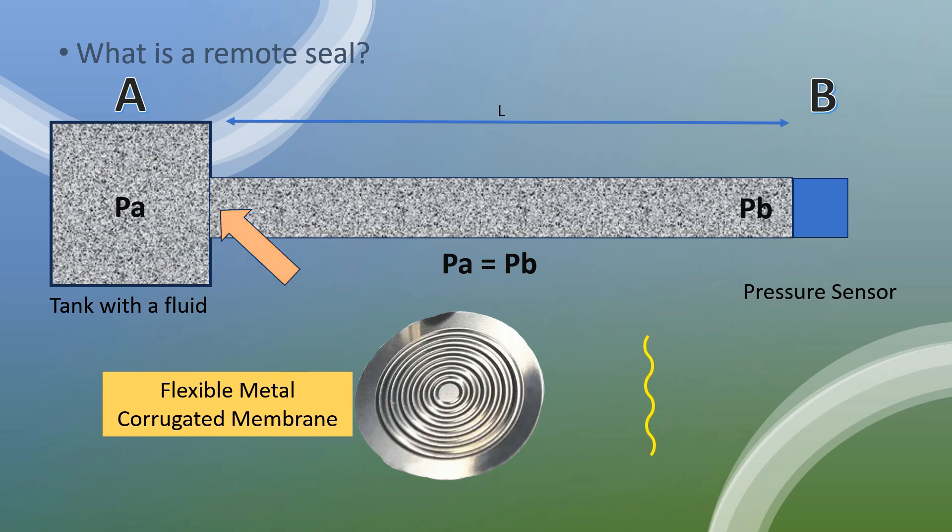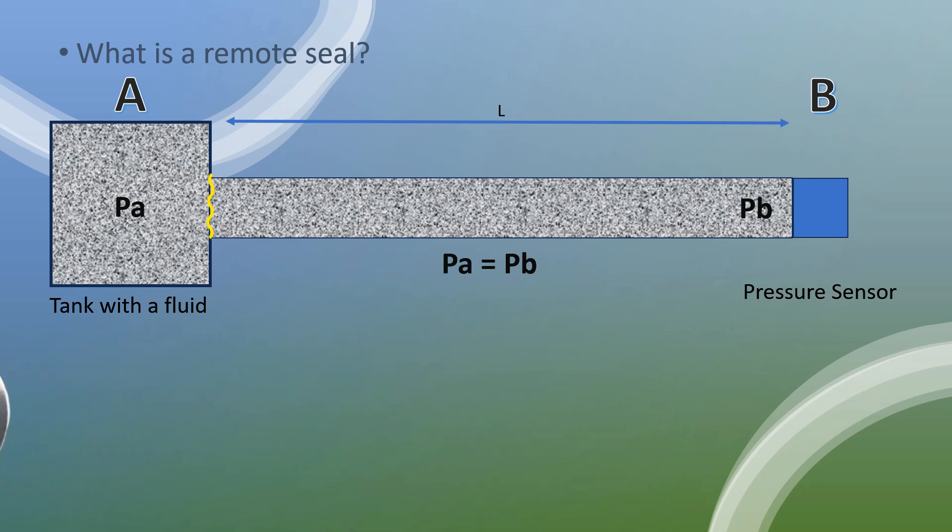Let's consider we want to separate point A from point B, not allowing the fluid to go all the way to the pressure sensor. For this situation, we can install this diaphragm in this position. We need to consider what is in this pipe. Because if it's gas, a small movement from the diaphragm will not reflect the pressure point A to point B.